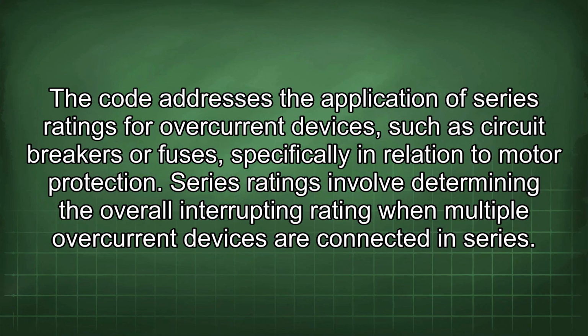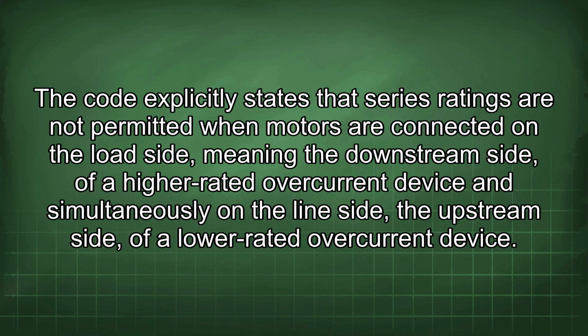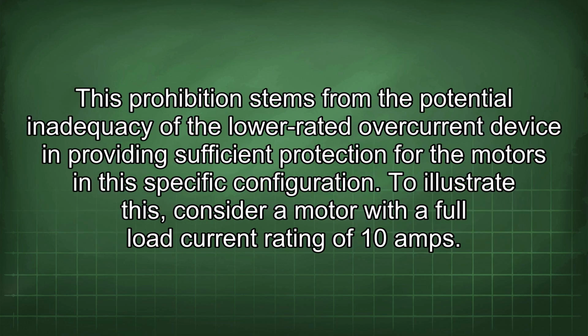Code addresses the application of series ratings for overcurrent devices, such as circuit breakers or fuses, specifically in relation to motor protection. Series ratings involve determining the overall interrupting rating when multiple overcurrent devices are connected in series. The code explicitly states that series ratings are not permitted when motors are connected on the load side, meaning the downstream side, of a high-rated overcurrent device, and simultaneously on the line side, the upstream side, of a low-rated overcurrent device. This prohibition stems from the potential inadequacy of the low-rated overcurrent device in providing sufficient protection for the motors in this specific configuration.